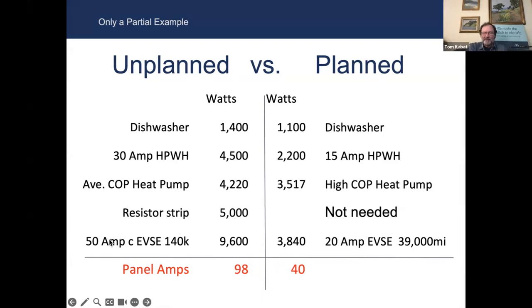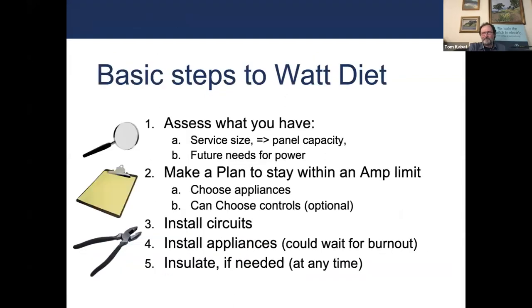Right-sizing the EV charger also matters - instead of a 50 amp setting and circuit, using a 20 amp circuit can still give you 39,000 miles per year. So with just these five end uses, not planning could soak up 98 amps, while planning and picking efficient equipment brings it down to 40 amps.